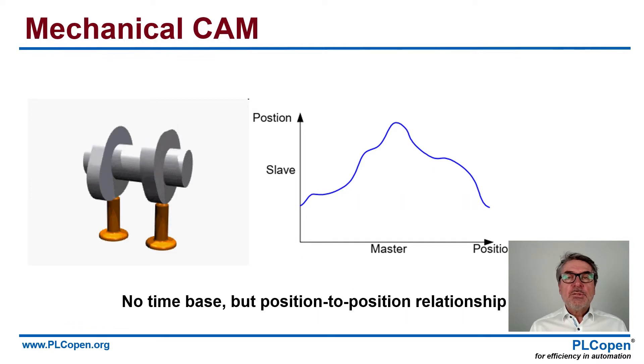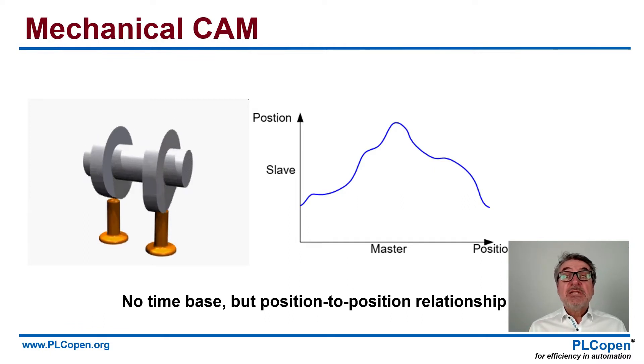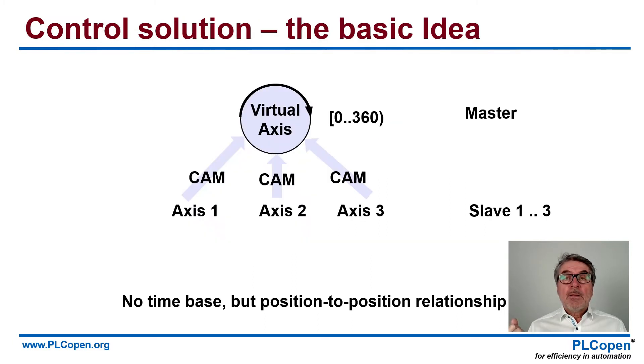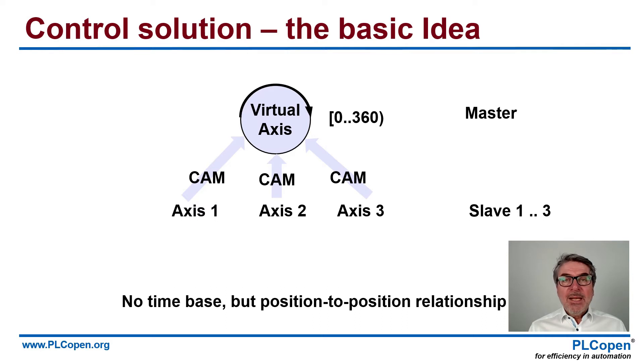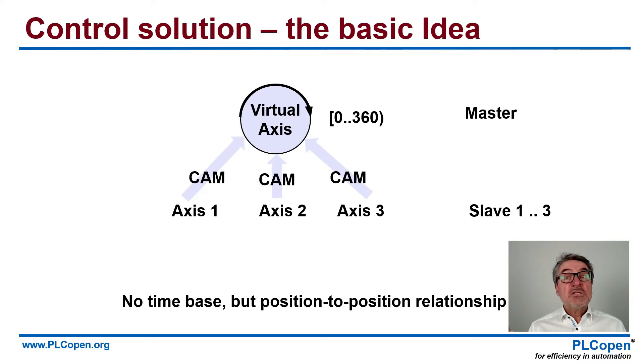If we look at a mechanical CAM, we have a position-position relationship between the master and the slave. If we convert this to a control solution, then the master can become a virtual axis and we link one or more slave axes to the master via a profile — in this case, a CAM profile. And again, this is a position-position relationship through the CAM profile.